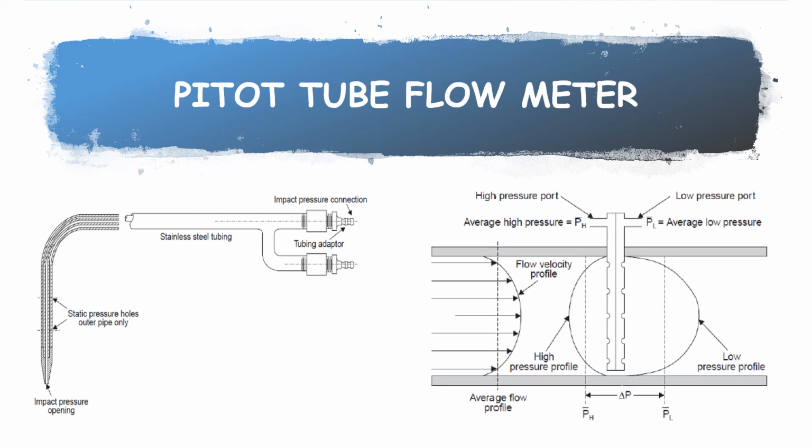The second diagram put up here tells you about the averaging Pitot tube, or the Annubar. To obtain a better average value of flow, special two-chamber flow tubes with several pressure openings distributed across the stream are available, as shown in this picture. These averaging elements are called annubars.